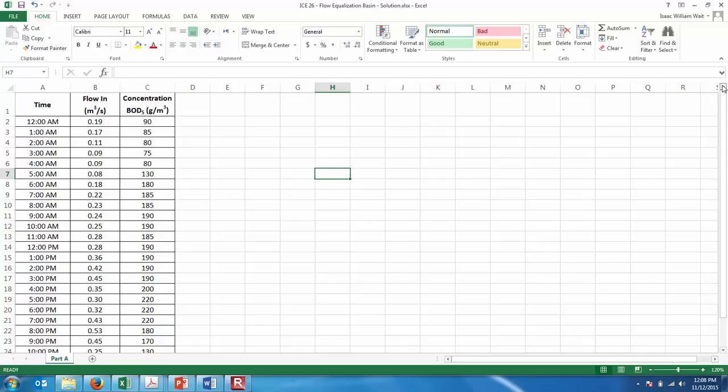This is flow rate as a function of time. We also have BOD concentration. In the middle of the night the flow rates are low — everyone's asleep, no one's flushing the toilet, so there's less flow coming to the treatment plant. Also the BOD concentration is low at night. What's getting into the sewer in the middle of the night is probably rainwater or groundwater seeping into cracked pipes. The concentration of BOD is lower at night, whereas at 7 p.m., everyone's throwing food down the garbage disposal, so BOD is very high.